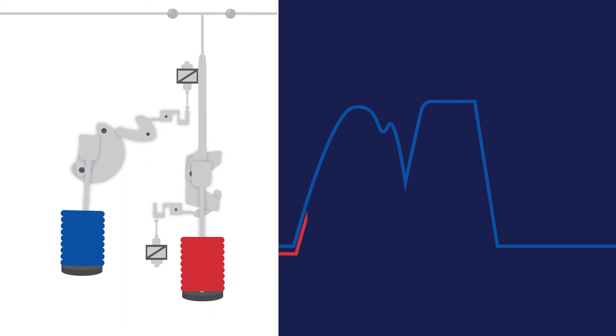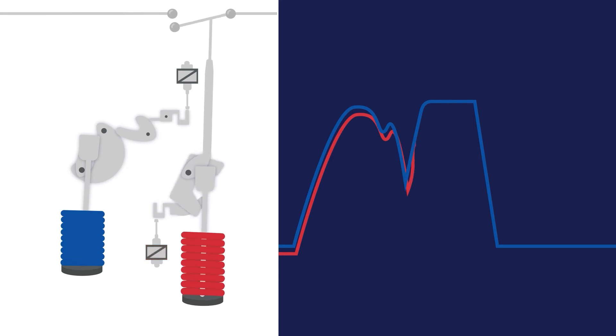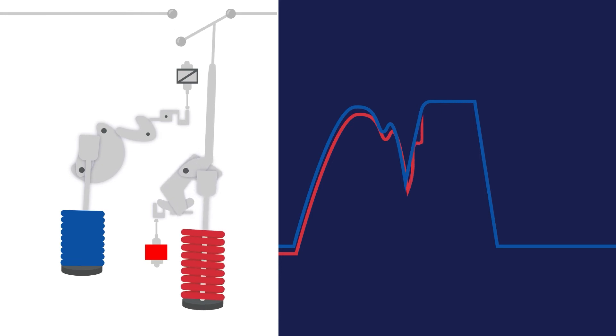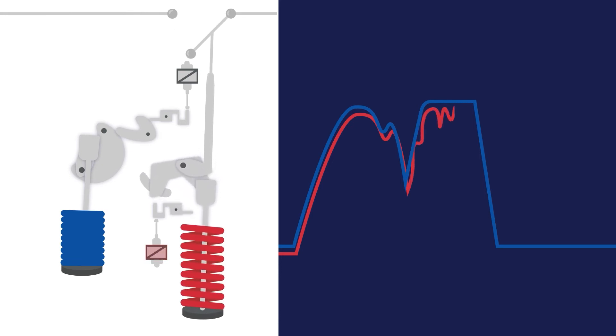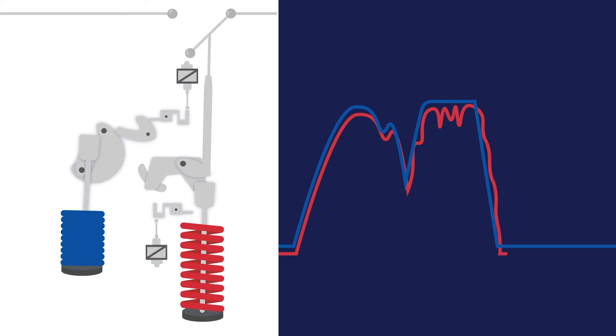Another common issue is with wiring connections or contacts within the trip circuit. It would be visible in the waveform capture as an erratic current signal on the graph when compared to normal operation. This would especially be apparent during the maximum current portion of the signature and at the falling current edge as the 52A switch opens.